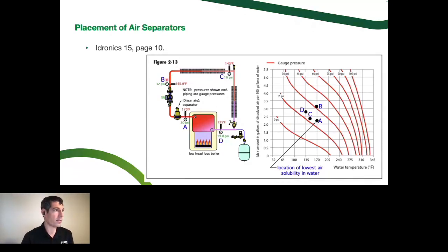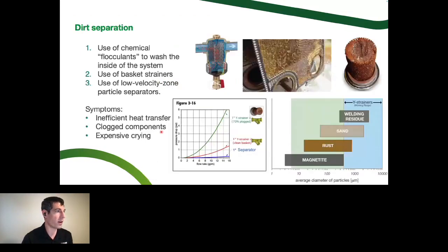So you could have an air separator that was sized properly, a high performance air separator in position B, and not get all of the air out of the system because it's coming back out of solution at position C or position D, and maybe is continuing to rust the boiler heat exchanger or something. So that's the third piece of the equation, it relates to where you put that air separator, and the hottest, lowest pressure is the correct spot there.